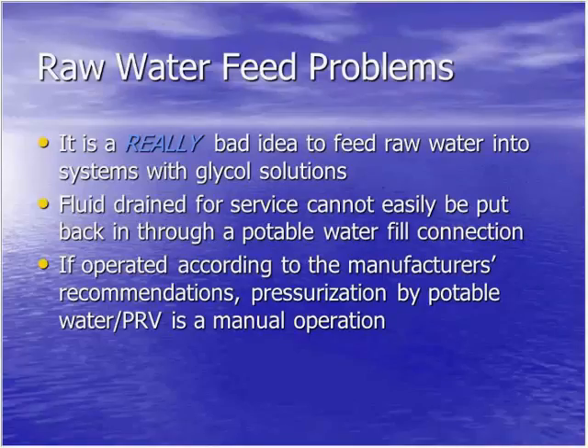So if all you put in is 30% glycol and you dilute that down, one, you won't have the inhibitors that are in there to protect the system from corrosion, but they're also in there to protect the glycol from degrading as well. So your glycol can degrade much quicker. It also leaves your system much more apt to culture bacteria. If there's oxygen and low concentrations of glycol below the minimum requirement, it can actually culture bacteria. Fluid that's drained from the system also can't be easily put back in through a potable water fill connection. And if operated according to manufacturer's recommendations, pressurization by potable water through a PRV is a manual operation. You manually have to go and open the isolation valve and top off your system pressure.